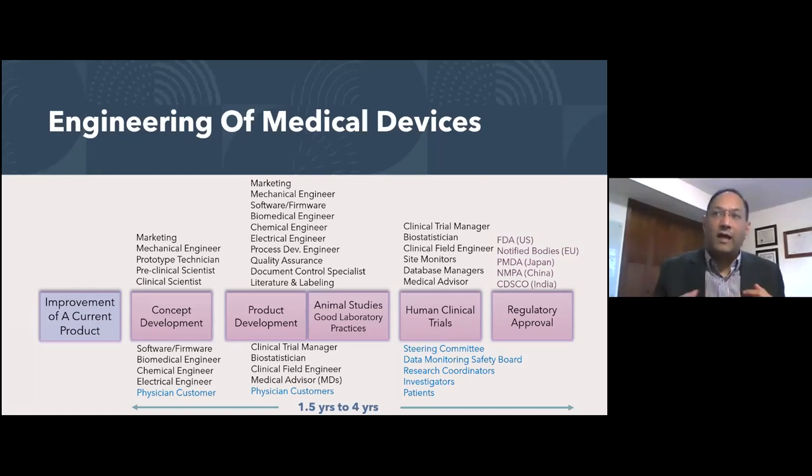They come in the form of design assurance and quality assurance, and they're tracking not just during development, but after the product is out in the field, for years until the life of the product. One has to be able to trace which batch of components came for a particular device at any point in time. Even before companies like Oracle or SAP had built databases, the medical device industry had built databases. So we know relational databases and that kind of work from years ago.